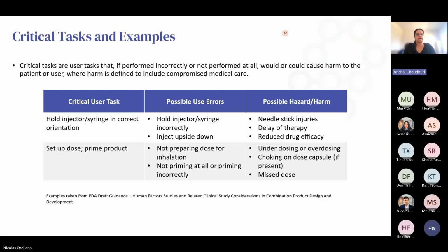So I wanted to go back to the definition of critical task. It is considered to be a user task that, if it is performed incorrectly or not performed at all, would or could cause harm to the patient or user, where harm is defined to include compromised medical care. And it's important to note that this definition is for combination products, and the critical task definition differs for combination products versus devices. For devices, critical tasks are defined as tasks that, if performed incorrectly, could cause serious harm.